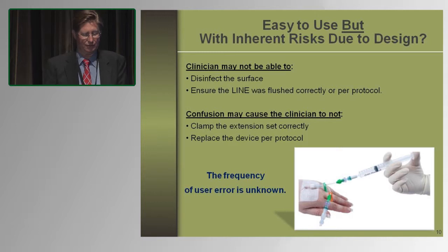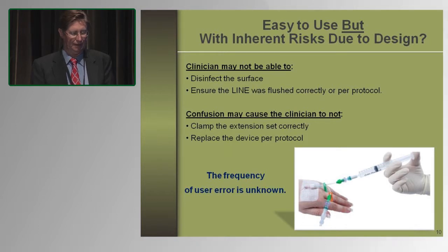These devices are easy to use, but there are some inherent risks due to design. For example, the clinician may not disinfect the surface of the connector. If they don't do that well, then the potential for introduction of organisms into the fluid path exists. Next is ensuring that the line is flushed correctly or per protocol. And there's confusion oftentimes by clinicians in understanding, do they clamp and then disinfect, or do they disinfect and then clamp? And then do they replace the device correctly according to protocol? And the frequency of these user errors is really unknown.